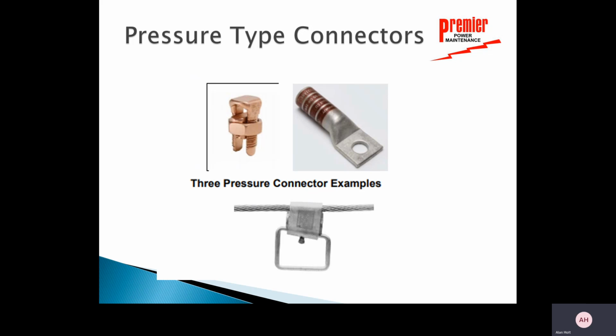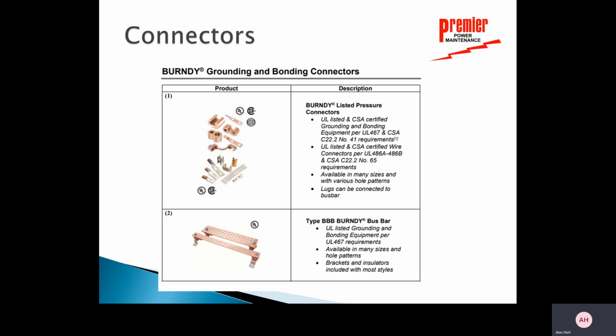So the pressure type equipment that we can see can be my split bolt. Okay, so I've got a split bolt there I can use. A split bolt right there. I can have a compression fitting. And I can have a wedge clamp. All of those are pressure type connectors. All of those are acceptable, if listed, for grounding and bonding.